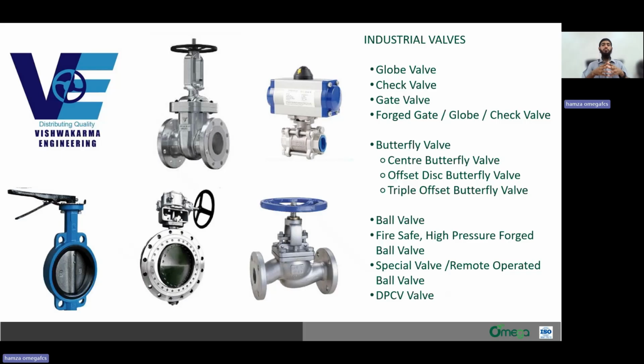Valves in water systems are crucial for controlling flow, pressure, and isolating sections for maintenance or emergencies. When the pressures are high and we see high temperatures, these high temperature and high pressure valves are very vital to the functioning of a power generation system. The key types of valves that we see here are the gate valves, the butterfly valves for flow regulation and isolation, ball valves for reliable shut-off of the system, and check valves for preventing backflow.